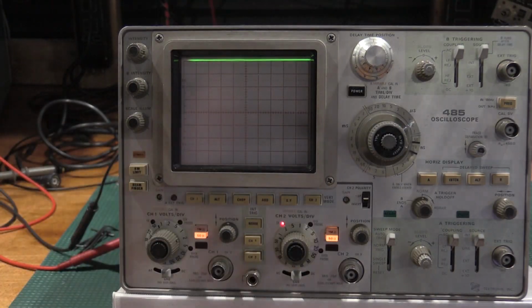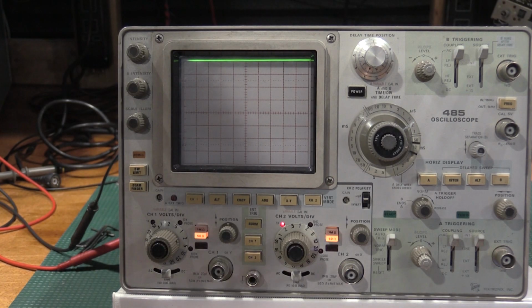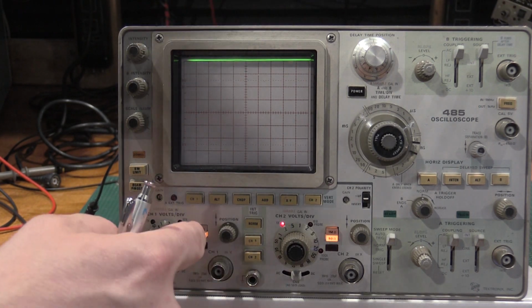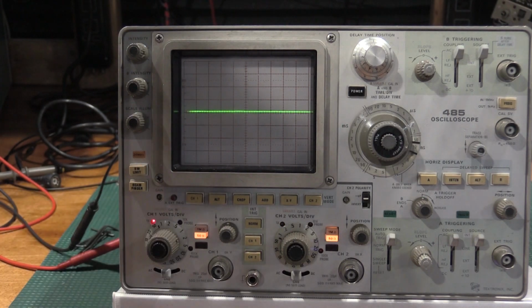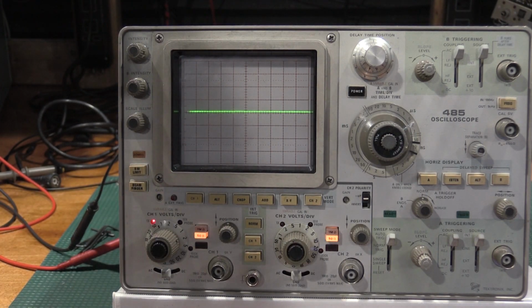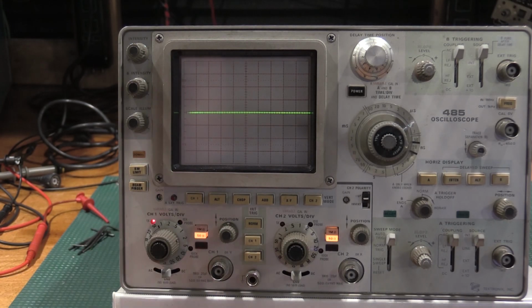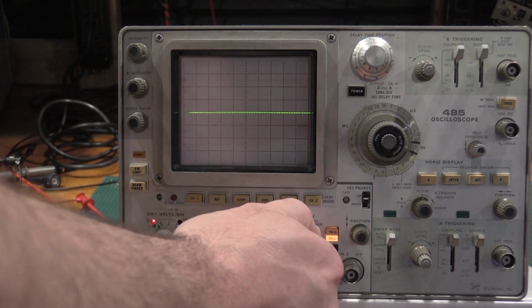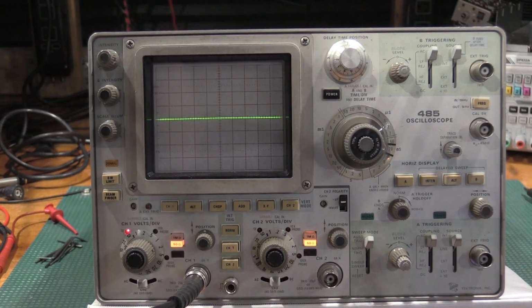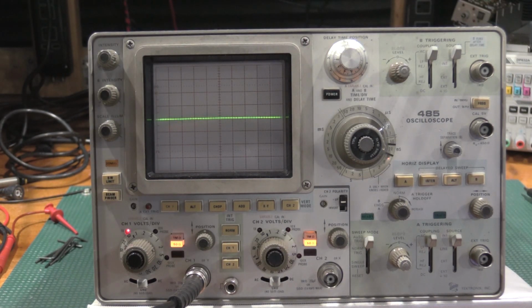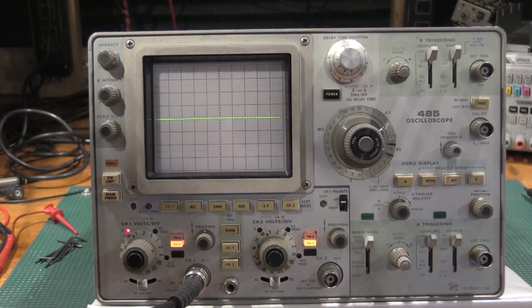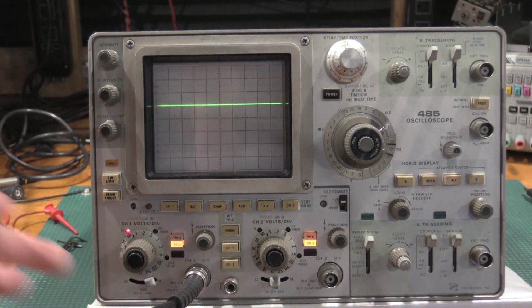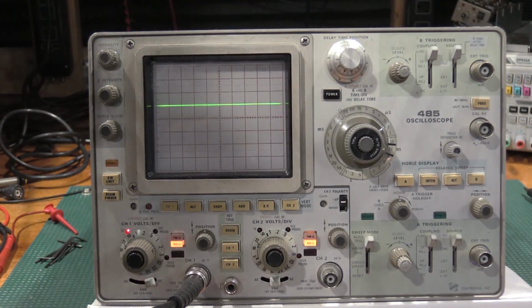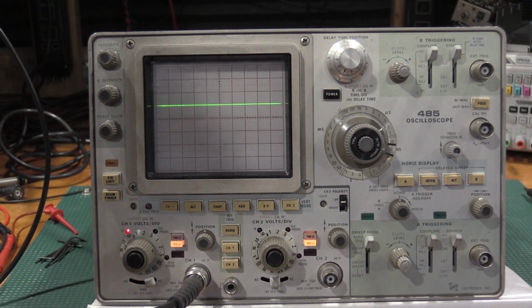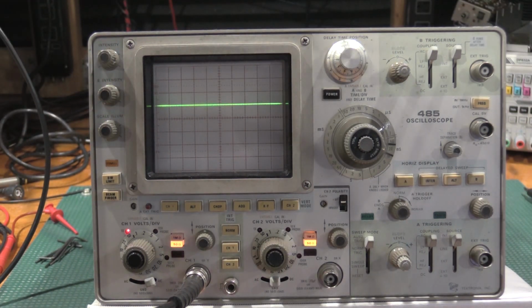Okay, we got to kick this over to 50 ohm. And they actually want me to test this on channel 1, which is fine. It needs to be on 50 millivolts. Do that too. Okay, I need to set the meter to ohm scale, 2-wire measurement. And the meter did not move at all. Or, it did move when I turned it on, but it only shifted up 50 millivolts, so our meter current is good.